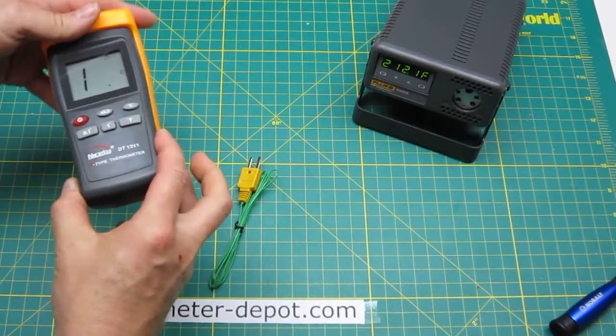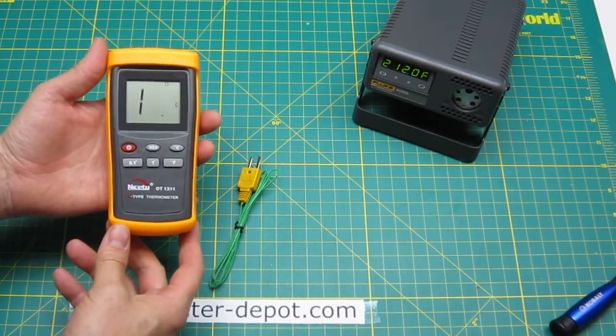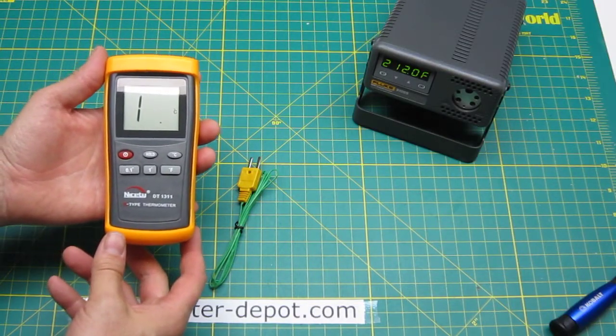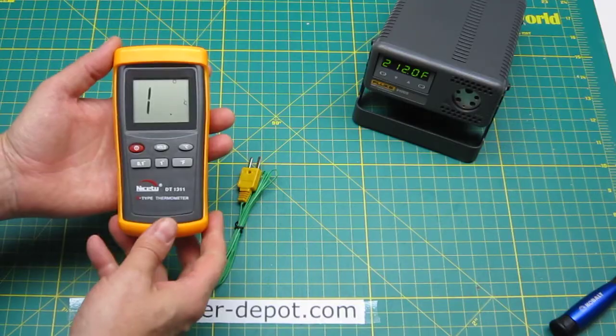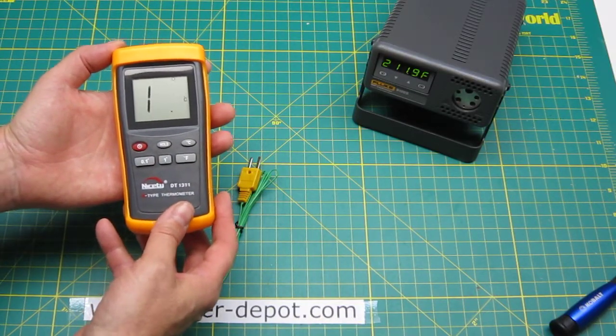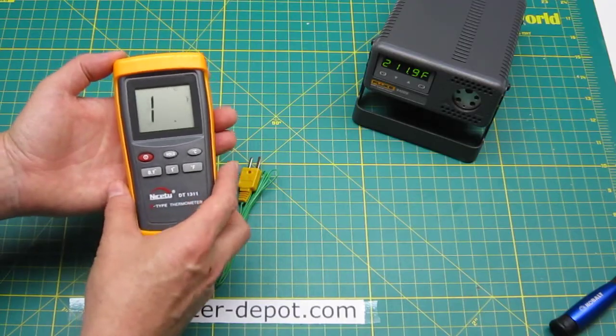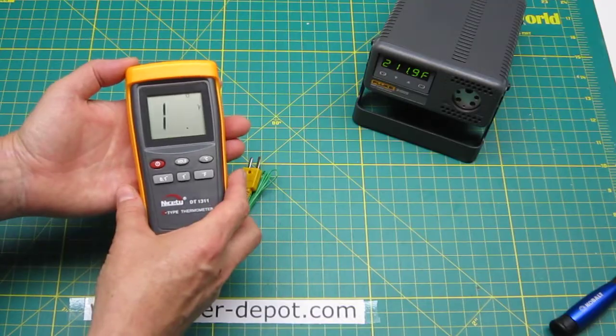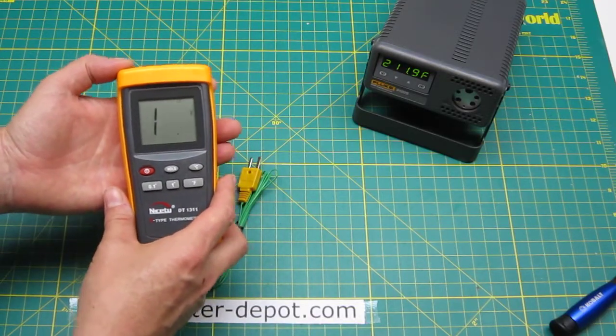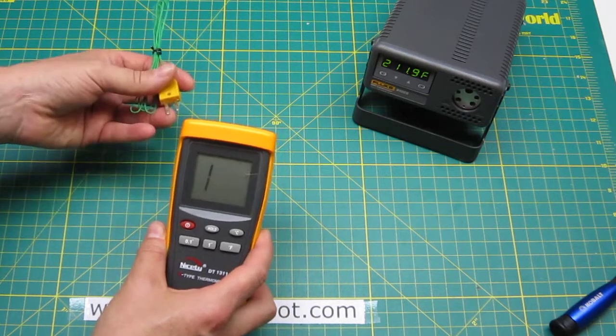Put the meter back into the bumper case and you are ready to measure. It always starts up in degrees Celsius and you can switch to degrees Fahrenheit very easily by just pressing the button. It shows a 1 at the moment because we don't have any thermocouple connected. Whenever it shows the 1 it means no thermocouple connected.